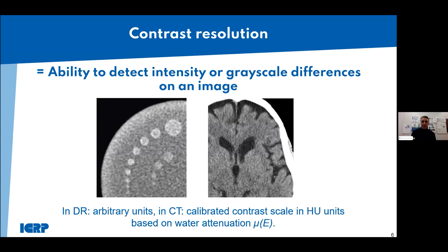Another key parameter, obviously, is contrast, which refers to our ability to detect intensity or grayscale differences on a radiological image. It can be in arbitrary units like in post-processed digital radiography systems, or as in CT, calibrated contrast scale in Hounsfield units based on water attenuation. Nevertheless, the contrast resolution is also combined with the resolution to provide detectability of clinical targets. Next one, please. However, the contrast and resolution targets are interfered by noise, which is fluctuations of image intensity values around their mean value. So this interferes with contrast detectability and detail detectability. So we are talking about a distractor.